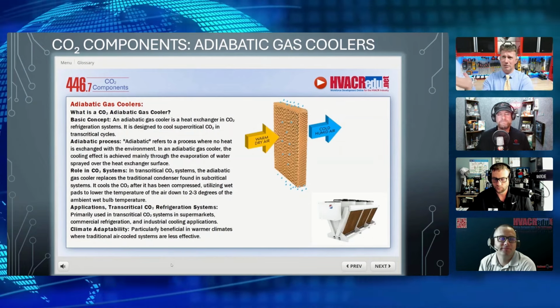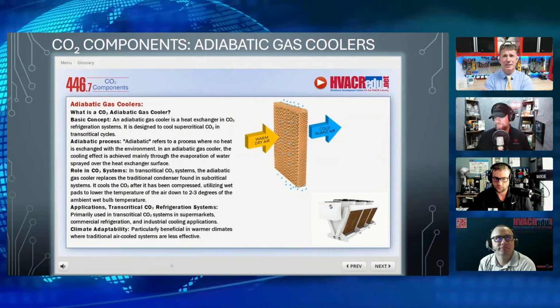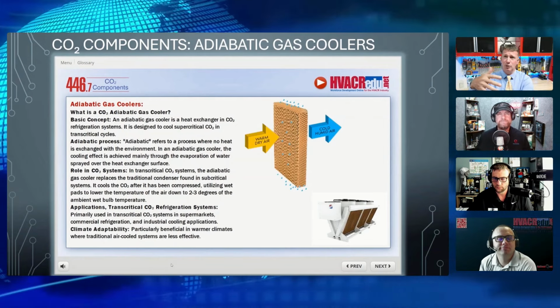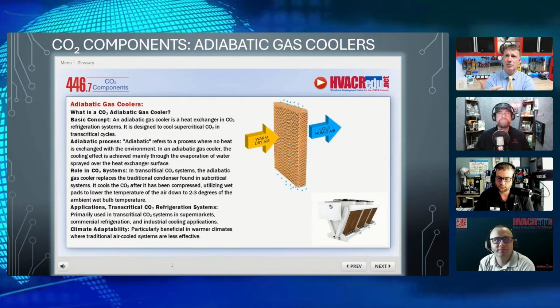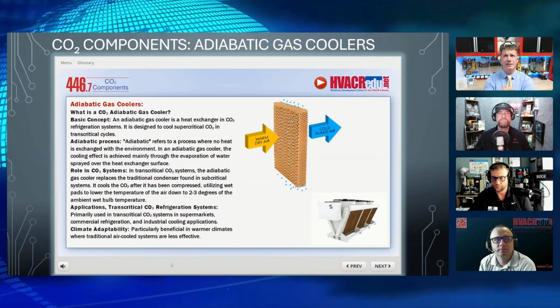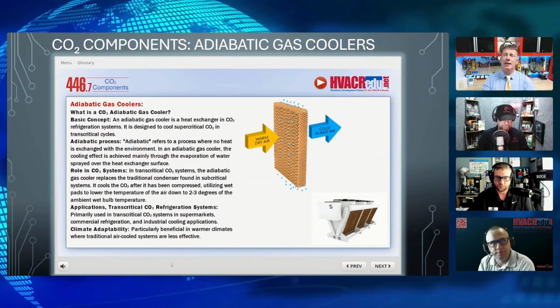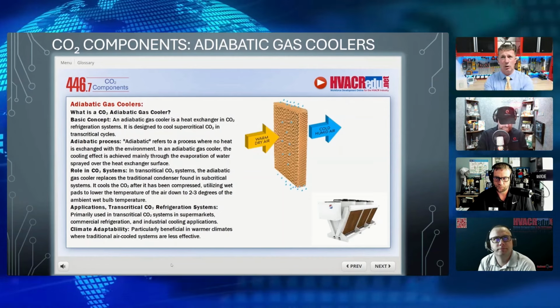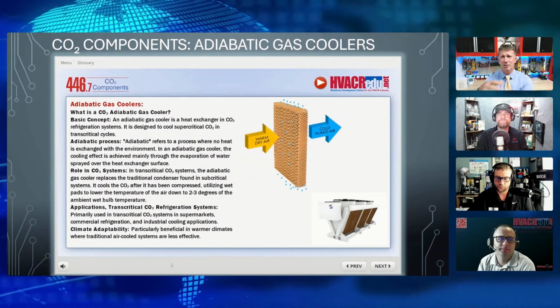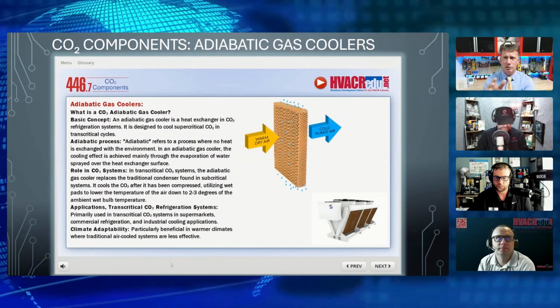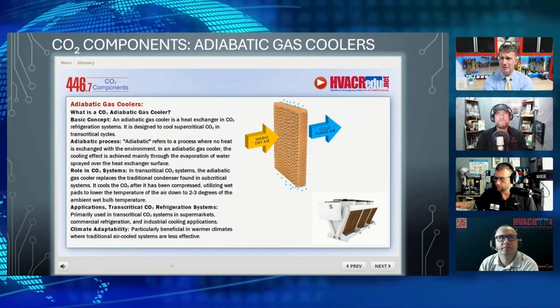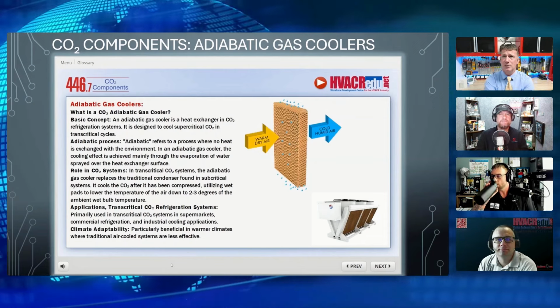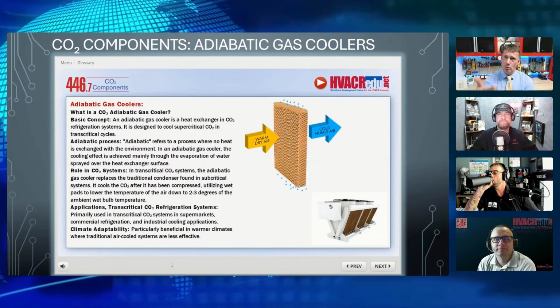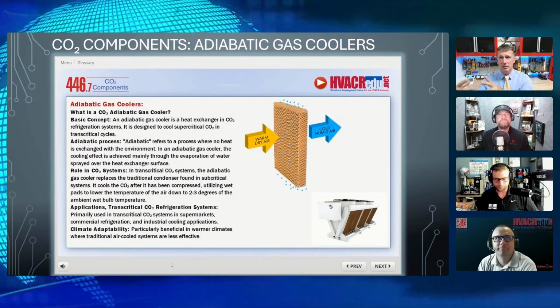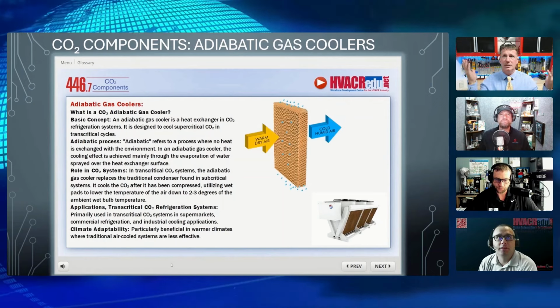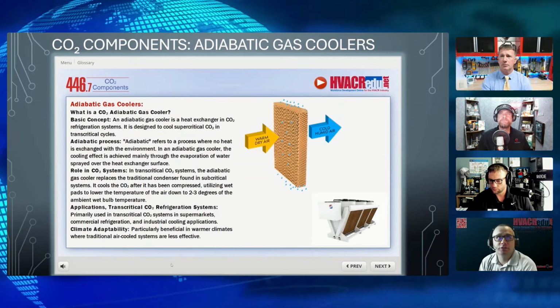You can walk into grocery stores and we've got relief valves in a variety of places, but typically they're not run to the roof because it's not been as much of a concern with the actual refrigerant itself. It's typically going to dissipate into a large space. With CO2, we're going to make sure we get those to the exterior. If you've ever walked on a grocery store roof, you're going to see relief valves on every refrigeration rack. Now we're just going to have more of them with different pressure ratings depending on where they are in the system. There are also relief valves on virgin refrigerant tanks.